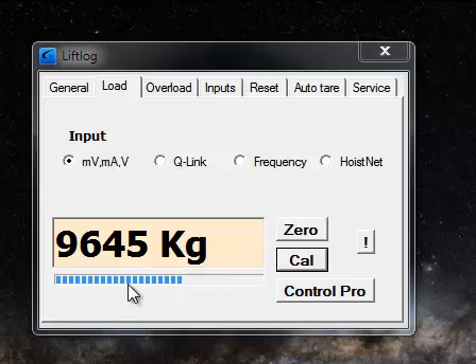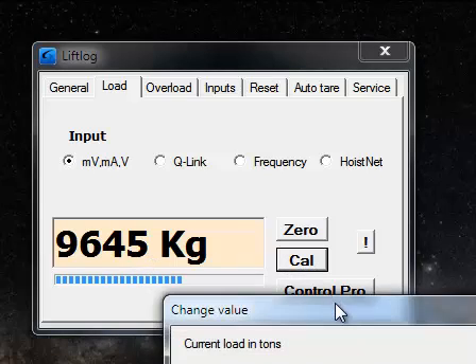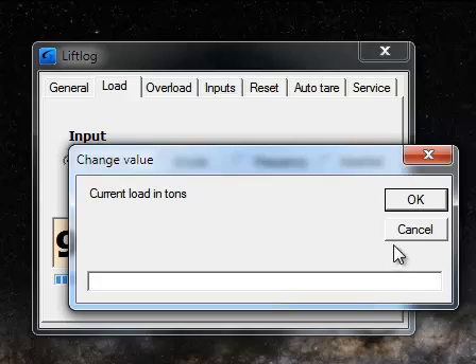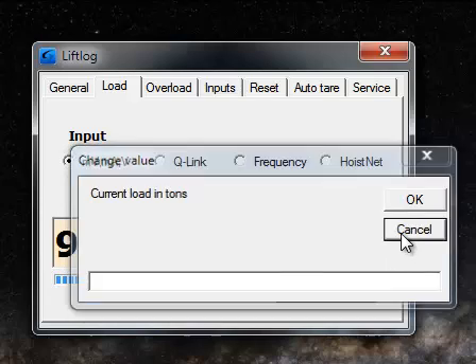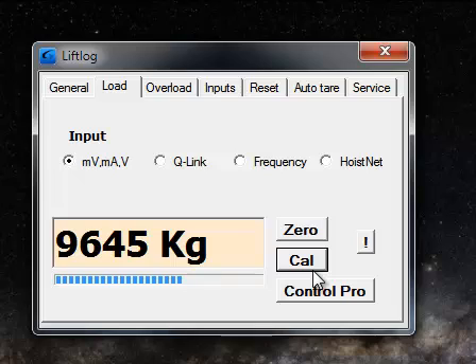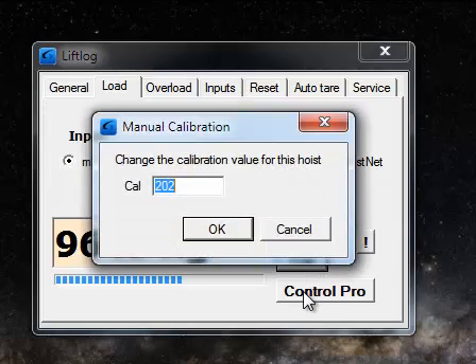Okay, but having done that, let's just say we've done a calibration at 10 tons and we're seeing 9.645 tons. Geez, we're not really happy with that. We'd like it to be a bit closer. Now we're familiar with hitting the cal button. When we hit the cal button, this screen appears and we key in a load and it calibrates. If I hold down the shift key when I hit the cal button, a different dialog box appears.